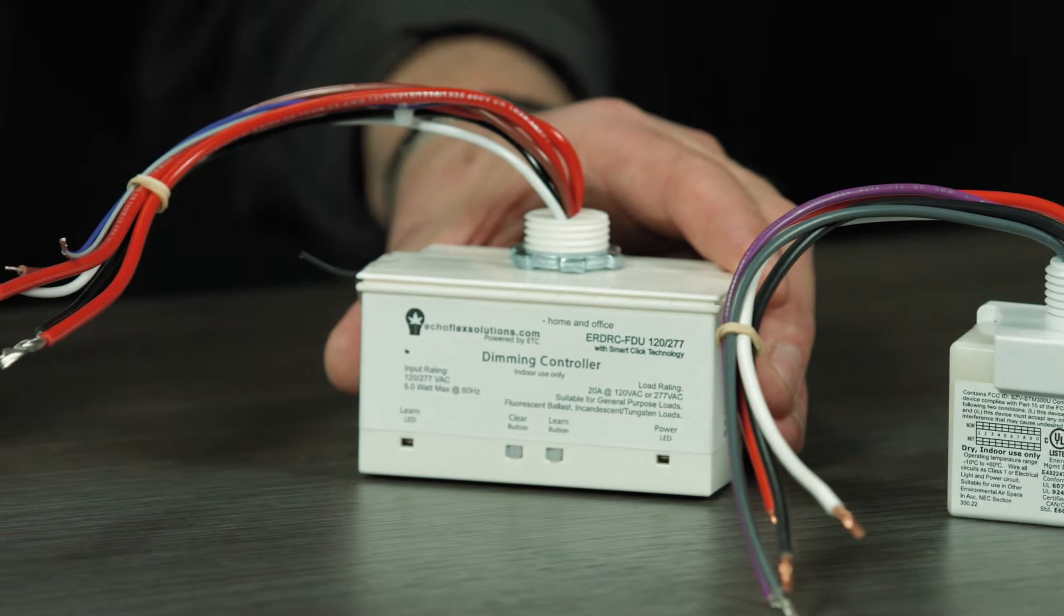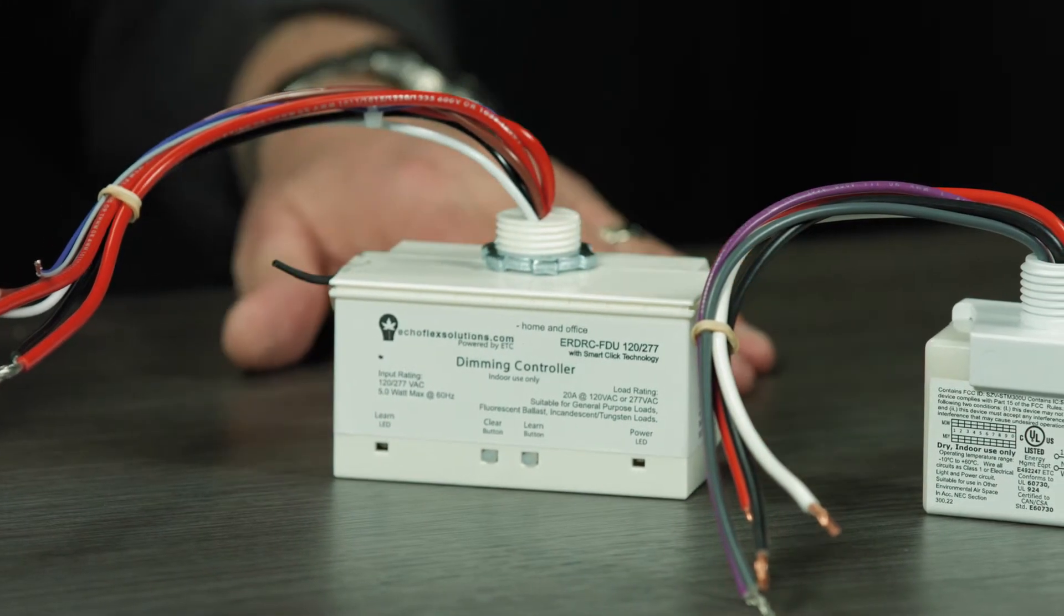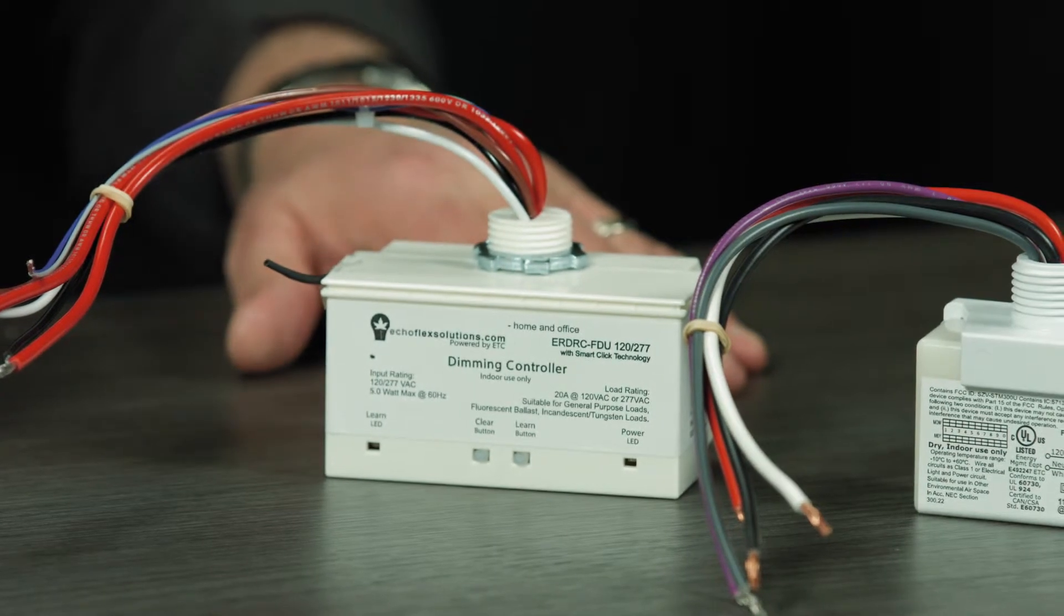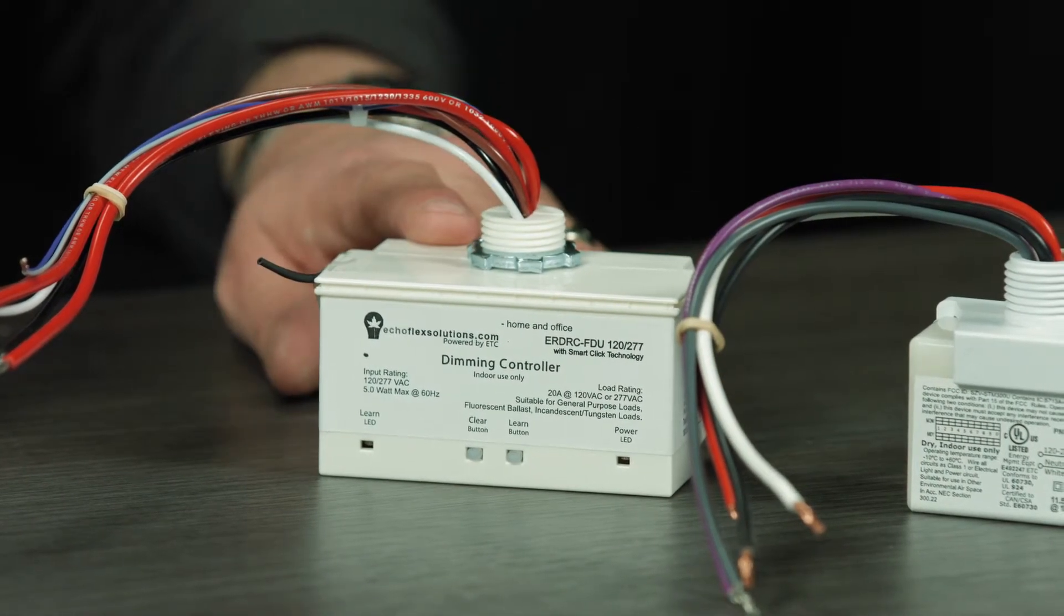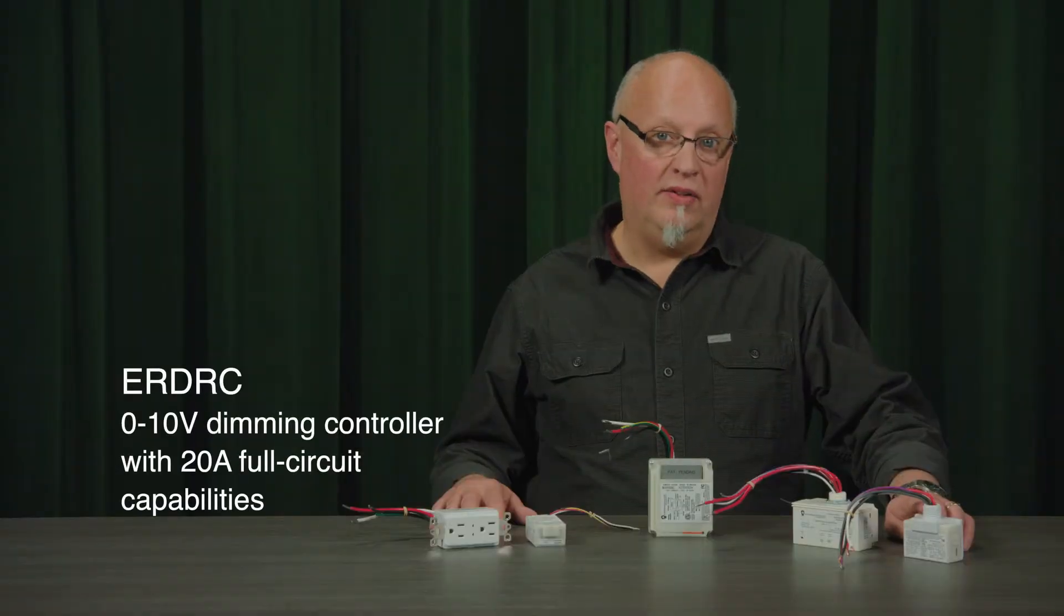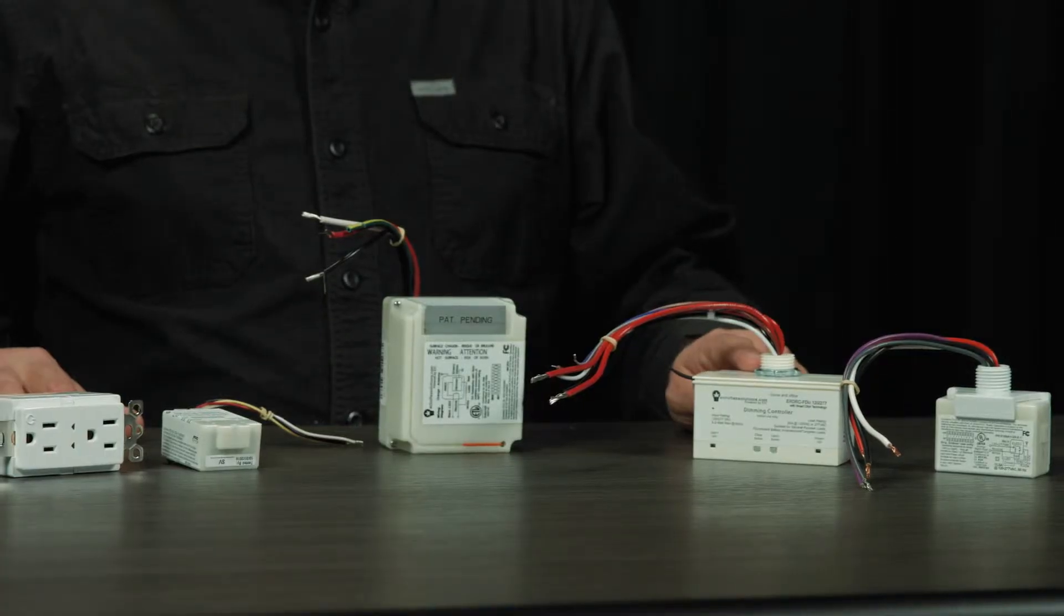Next one in line is the ERDRC-FD or FC. It is also a power pack style 0 to 10 volt dimming controller. It has a 20 amp relay in it. The E-LED1 has an 11.5 amp relay, so this guy is applicable for full circuit control. Available with 120, 277 or 347 volt for Canadian applications.